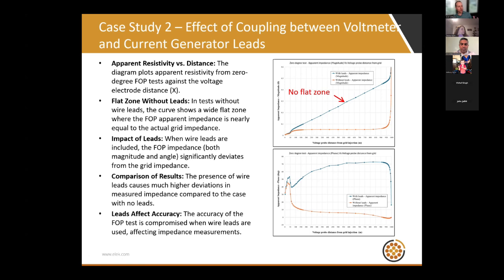In fact, we have no flat zone. So it's really difficult or impossible in a practical sense. If we did this test practically, we would have no flat zone, so we couldn't actually determine what is the ideal apparent impedance. What's the actual apparent impedance? Because we have no flat zone.